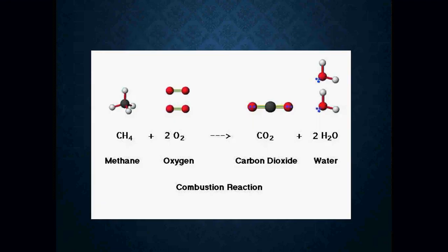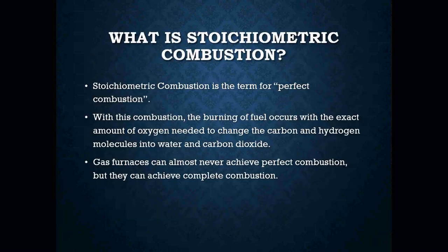In perfect combustion, I'm going to have carbon dioxide, water vapor, and energy as my byproduct of combustion. This is when the burning of fuel occurs with the exact amount of oxygen needed to change those carbon and hydrogen molecules into water and carbon dioxide.